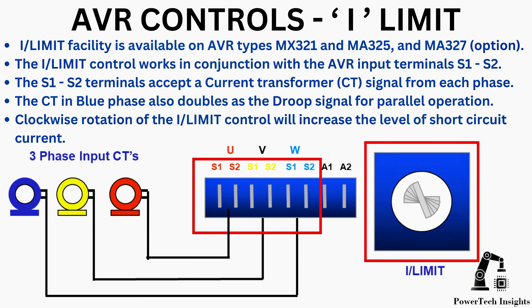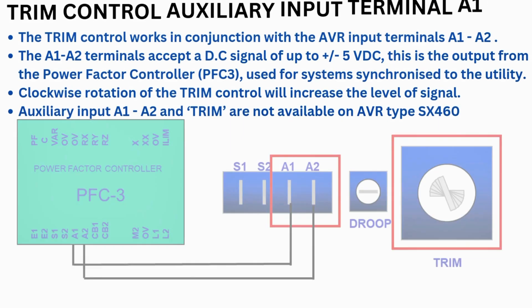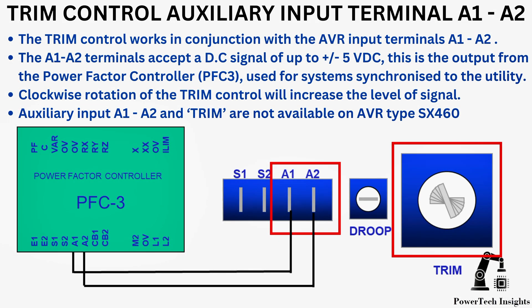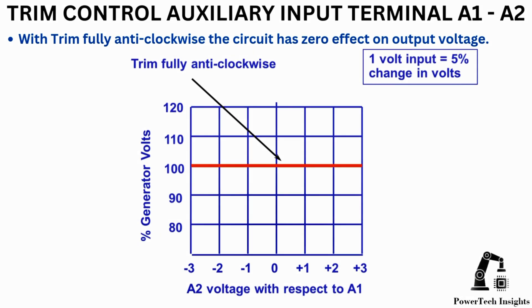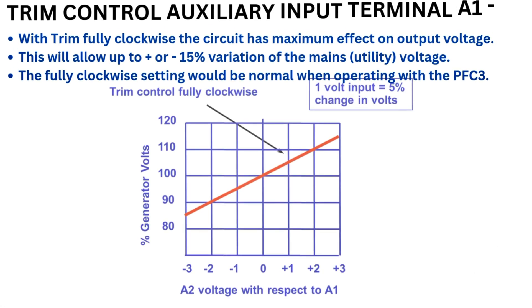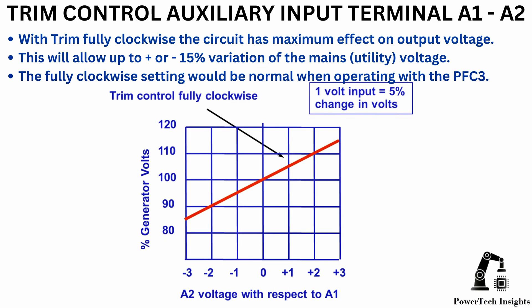Trim control, auxiliary input terminals A1, A2. The trim control works in conjunction with the AVR input terminals A1, A2. The A1, A2 terminals accept a DC signal of up to plus or minus 5 VDC. This is the output from the power factor controller, used for systems synchronized to the utility. Clockwise rotation of the trim control will increase the level of signal. Auxiliary input A1, A2, and trim are not available on AVR type SX460. With trim fully anti-clockwise, the circuit has zero effect on output voltage. With trim fully clockwise, the circuit has maximum effect on output voltage, allowing up to ±15% variation of the mains utility voltage. The fully clockwise setting will be normal when operating with the PFC3.